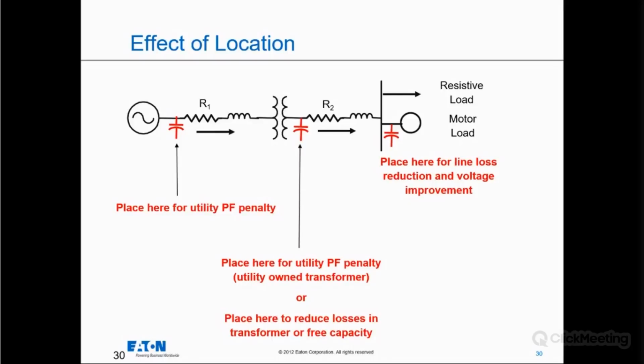And the larger power factor correction units placed at the common point of coupling, that business has been increasing over recent years. And there's a couple of reasons probably for that. One, if you know a lot about power factor correction, harmonics and power factor correction products don't play well together. So if you have air compressor loads, typically who has come in and tried to sell you what piece of equipment, there's probably been a variable frequency drive salesperson in there telling you how much money you can save by putting a VFD on that air compressor.